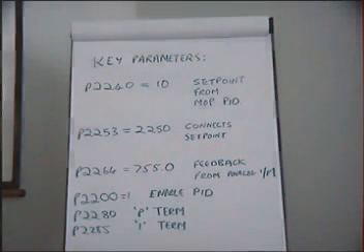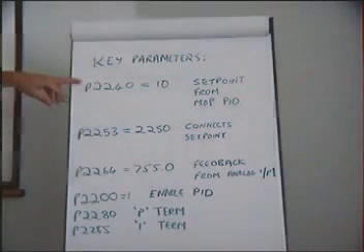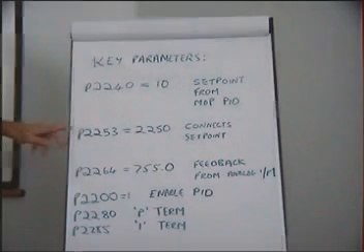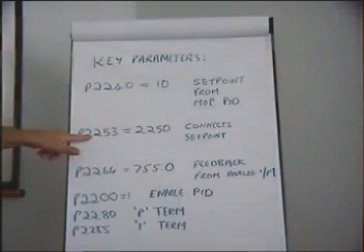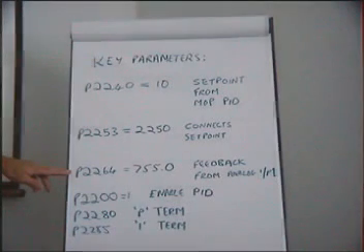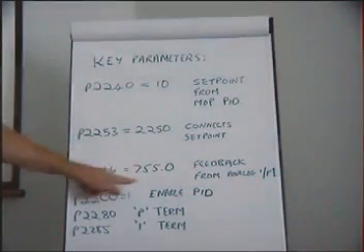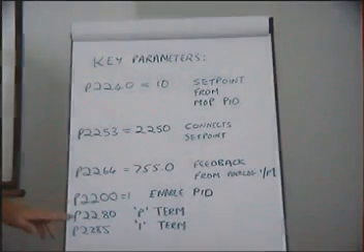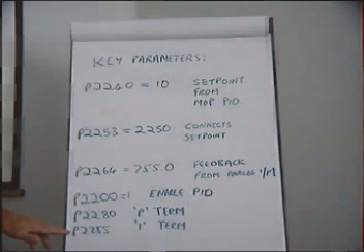Here are the key parameters we're starting with. The setpoint is 10%. We're connecting that setpoint to the PID setpoint. The feedback, which is coming in via the analog input, we're connecting here. We switch on the PID with 2200. And then we can adjust the P and I terms to tune the stability of the system.